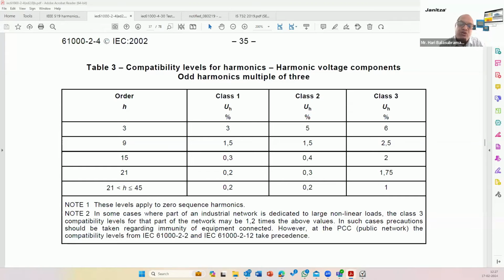For example, if you use a very good VFD but load it only 50% or 70% of the time, or less than 20% loading on the VFD, then naturally the total harmonic distortion would be much higher than what was actually planned for in the VFD. So it depends on the choice and selection of the ratings, and on the choice and selection of the location where you are installing these devices.